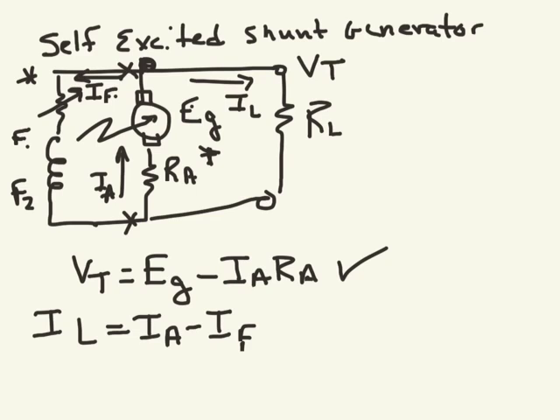Last thing I want to add to this video is just something that happens as we really start to push IL. When this thing starts to reach rated current, what we're looking at is a terminal drop due to this equation right here. But when we get a terminal drop, we're also going to get a voltage on the field drop. So now we're losing field, which would cause an even larger drop in VT, because as field falls off, EG falls off, and that seems like a vicious little cycle. So we'll have to actually look at some characteristic curves for generators and see how vicious of a drop-off this really is. And we will see, as we start to fall off at that terminal voltage, we'll lose some field, and EG and then VT will fall off even more.